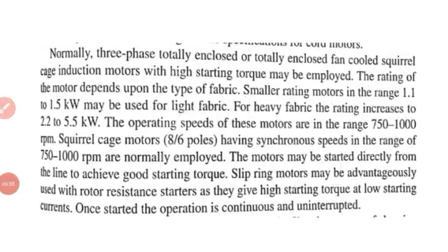I will continue now, as I am discussing slip ring induction motors. Slip ring induction motor means we are adding external resistance to the rotor circuit, so that the starting torque will be high. Once the motor has accelerated, we can remove the rotor resistance, because otherwise power loss will take place in the rotor resistance. So we can avoid it, and for higher starting torque purposes, slip ring induction motors can be used.